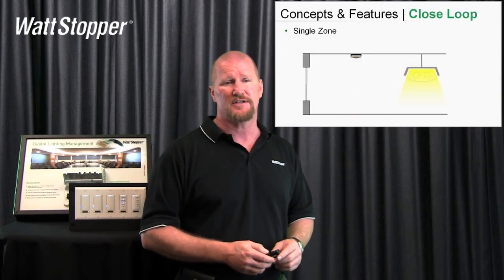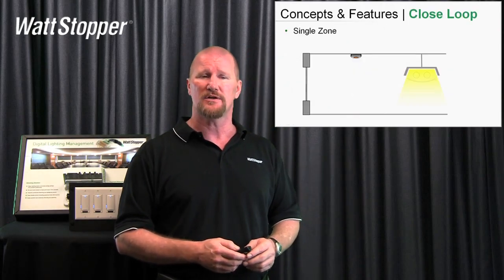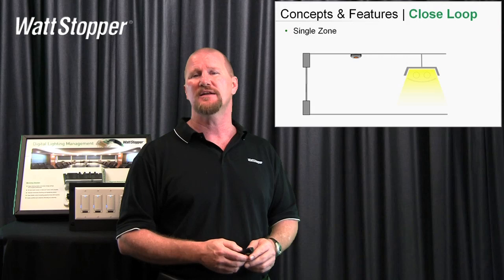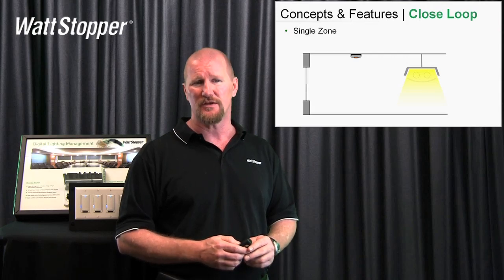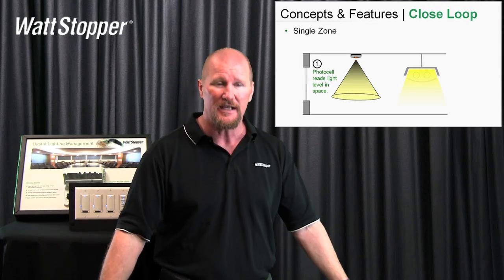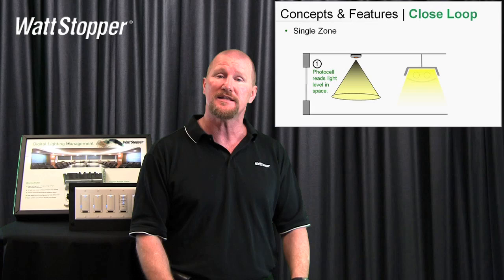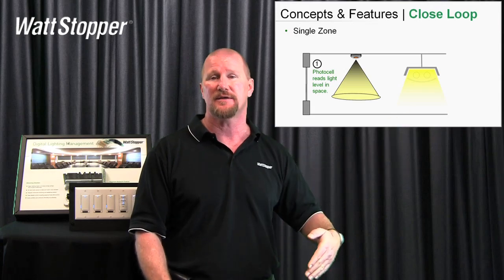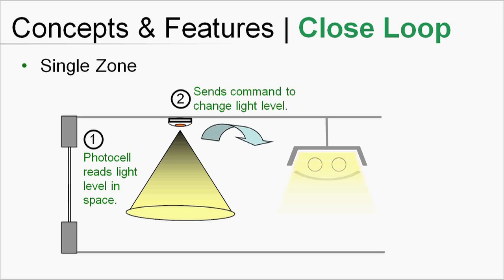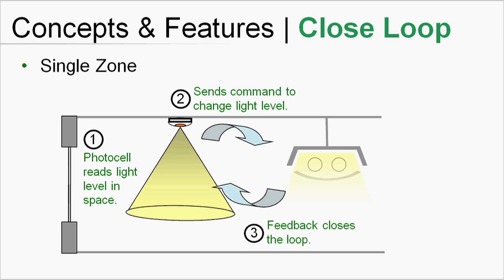Closed loop is the first one I want to talk about. By this great artist rendition, you'll see that I've got the photo sensor up in the center and I've got a pendant-hung light fixture. The photo sensor looks down into the space — this is the big distinction with closed loop. It's looking down into the space and it's going to take into account the electric light that's hitting there and any natural light coming in from the window. It then sends a signal to the light fixture which changes the light level, and then the photo cell sees that change, so the loop is closed.